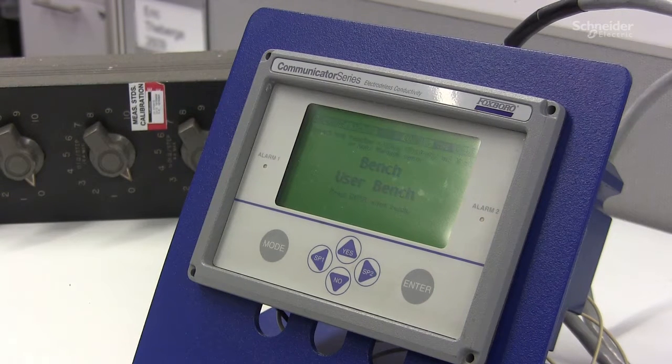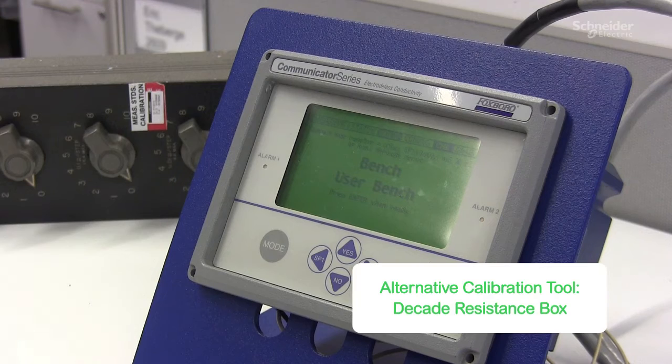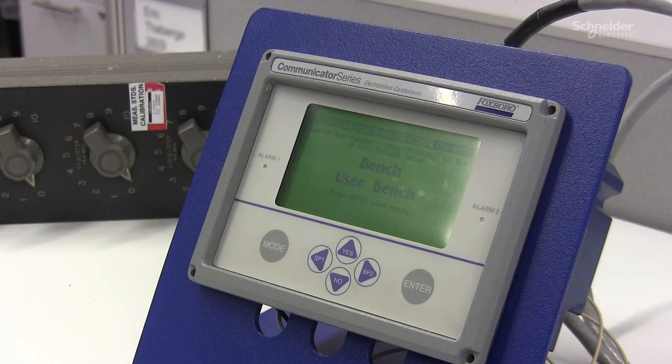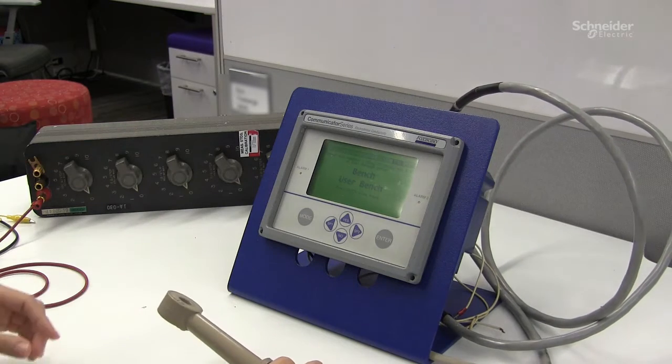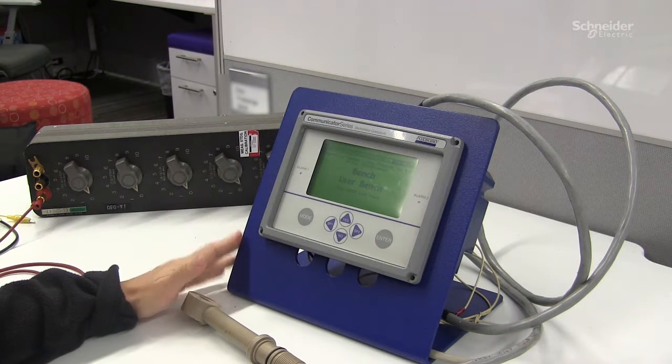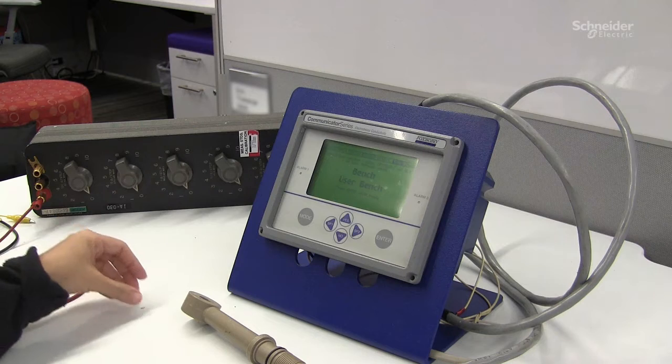So if you do not have a calibration plug, you need to have a decade box. But for you to use a decade box to calibrate your sensor, you need to apply some mathematics in a formula that is explained in the MI 611-224, that is the MI for the 875EC analyzer.